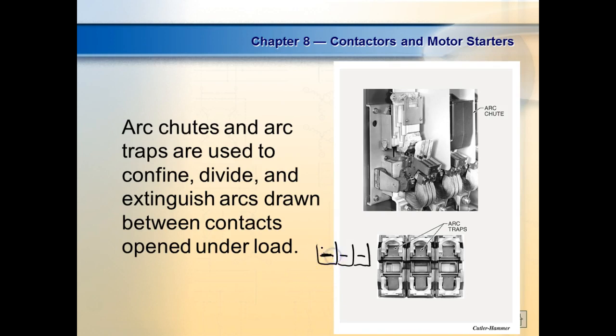Plus, what happens is when these contacts open, if we open them fast, it has a tendency to pull a puff of wind through those contacts inside this narrow groove. Kind of like when you're in a swimming pool and you open your hands real fast and the water comes swirling into the center real fast. So most of your newer contactors are going to have each contact within a channel. That way, if you get an arc and create ozone on this one, it won't cause the one next to it to arc, right?